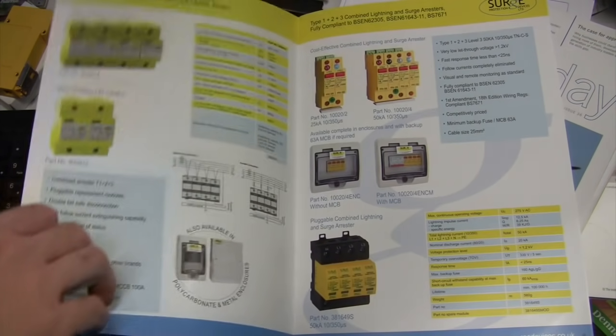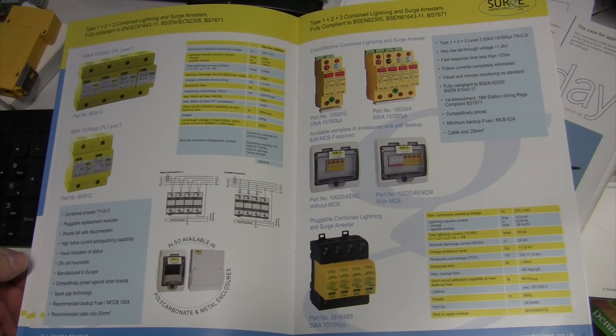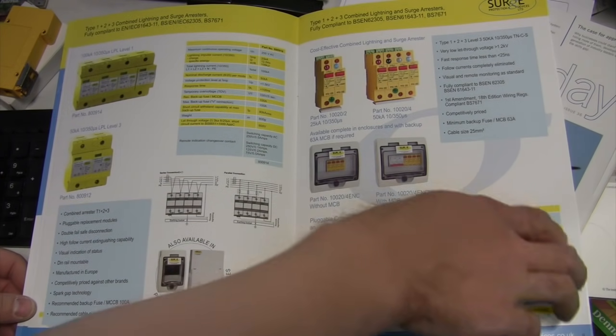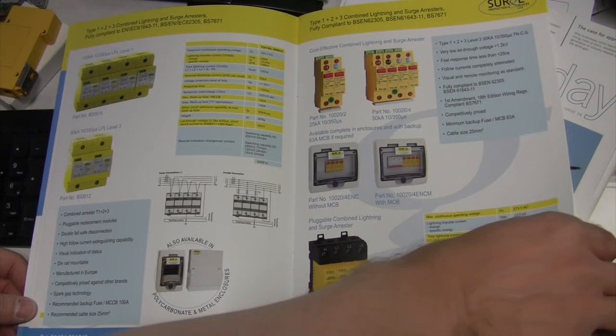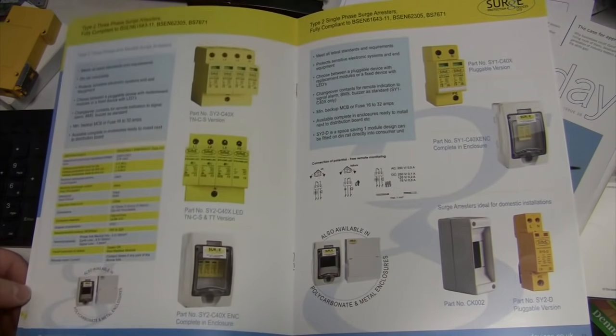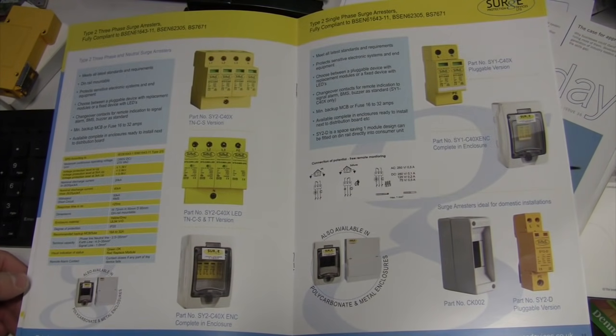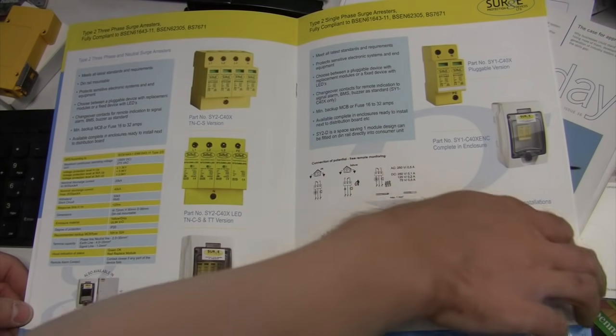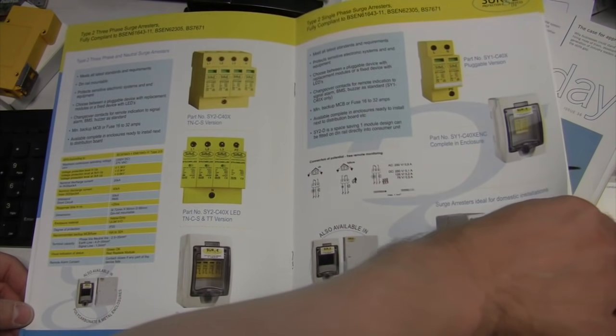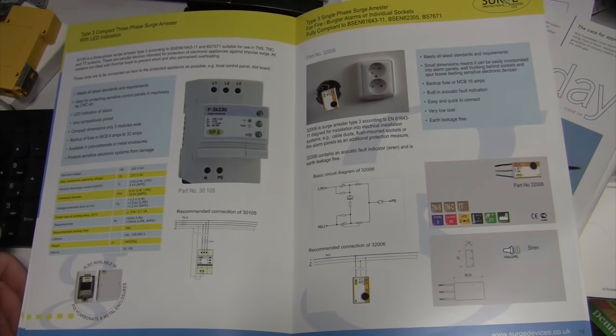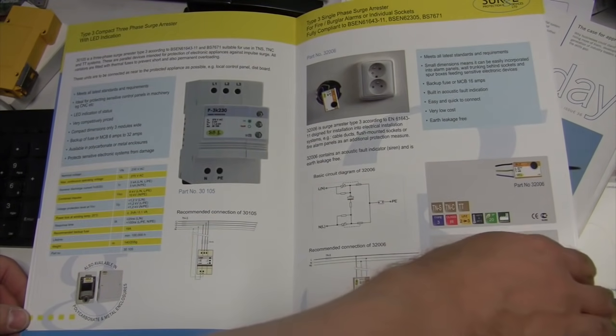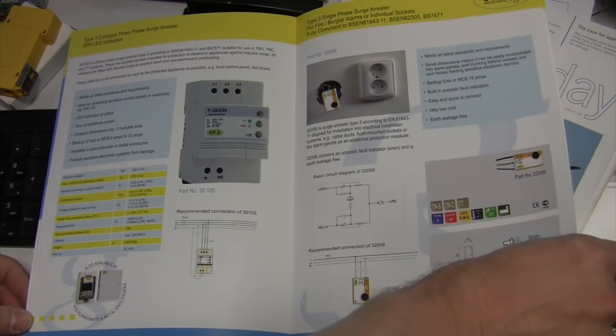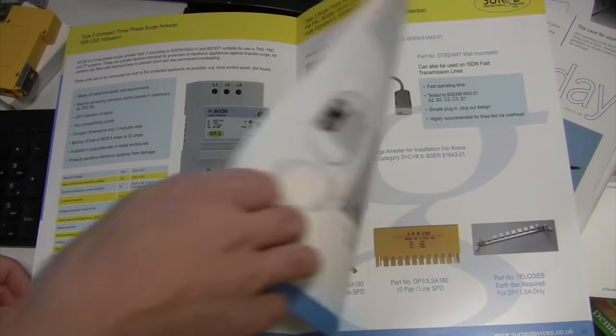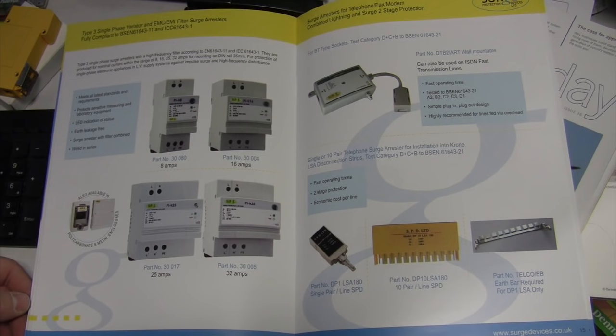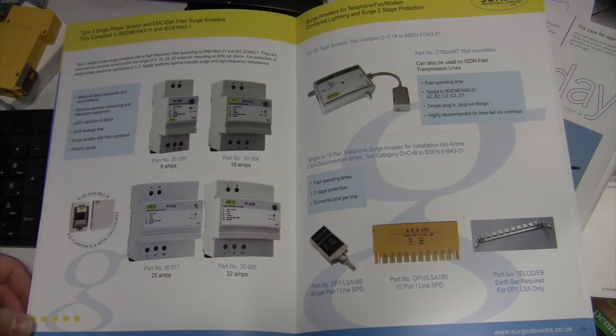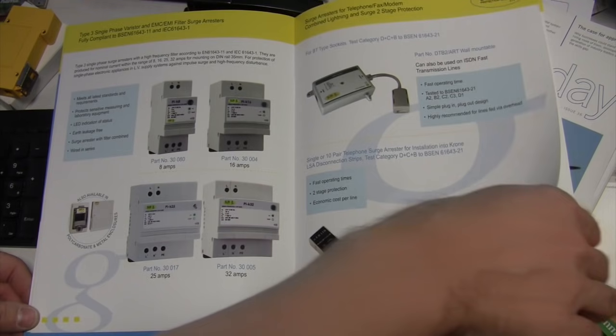Off-the-shelf consumer units, whether empty or fully loaded, are supplied without an SPD and often with little consideration for the retrofit of such. And in the competitive market of domestic installations where dickhead chancers, cowboys, unqualified builders and such are spunking consumer units onto the walls with little or no regard for the wiring regulations and at a price that undercuts legitimate installers, well, it's hard to justify adding in extra part costs unless the client has expressly requested such additional functionality. Which they generally don't when it comes to SPDs, as Jill and Joe Schmo out on the street probably have no idea these devices even exist.